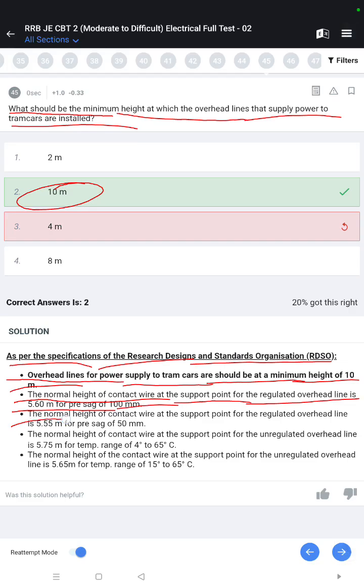The normal height of contact wire at the support point for the regulated overhead lines is 5.6 meters for pre-sag of 100 mm. The normal height of contact wire at the support point for the regulated overhead line is 5.55 meters for pre-sag of 50 mm.